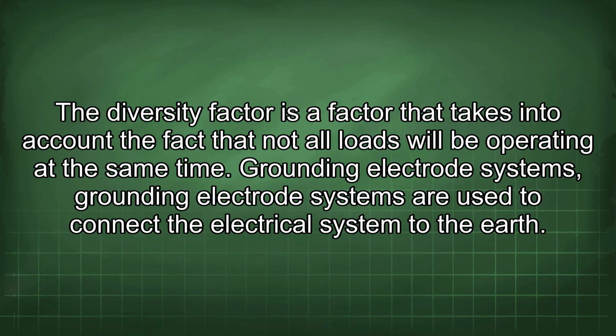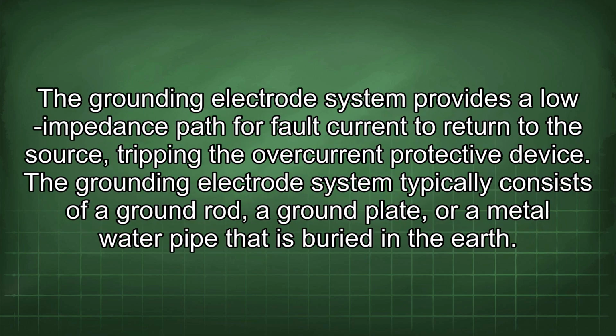Grounding electrode systems are used to connect the electrical system to the earth. The grounding electrode system provides a low impedance path for fault current to return to the source, tripping the overcurrent protective device. The grounding electrode system typically consists of a ground rod, a ground plate, or a metal water pipe that is buried in the earth.